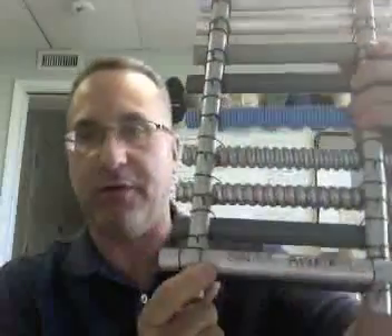He used tie wire to mount these conduits to the frame, and he used just the right amount. You don't have to go crazy with the tie wire — just the right amount. Very symmetrical, very safe, and he did a great job. I like the way he labeled it and put his name on it, which is always a good thing.